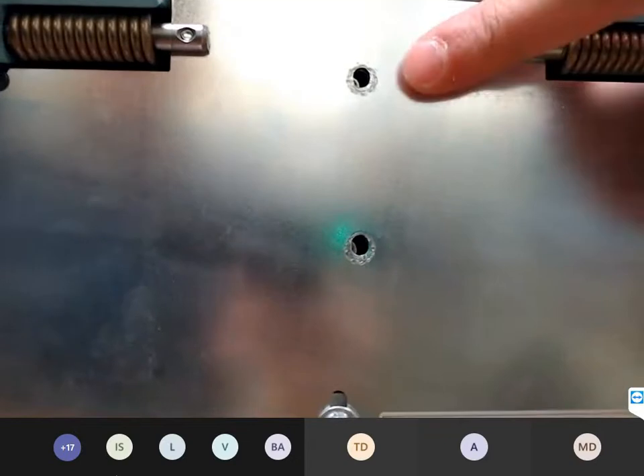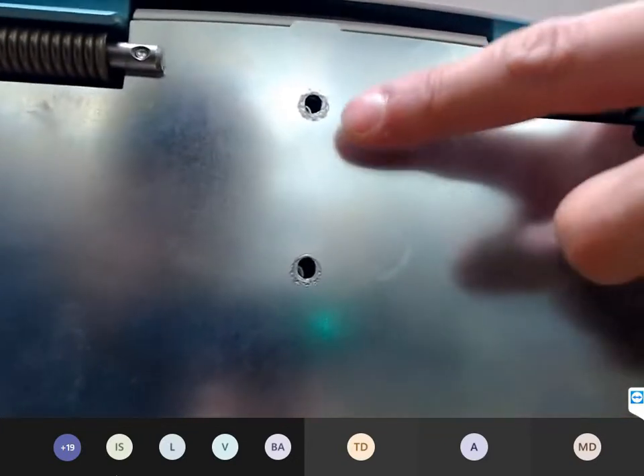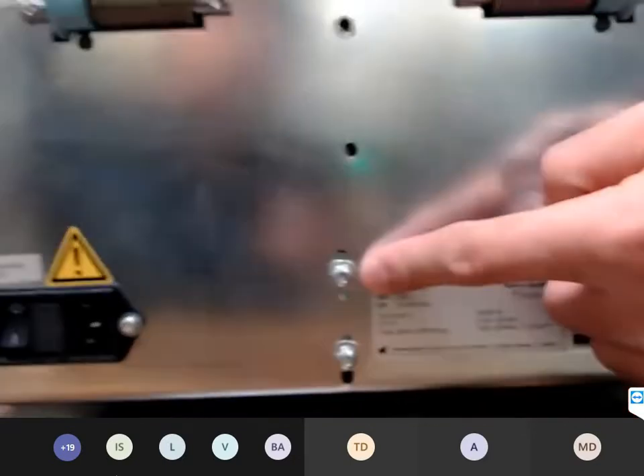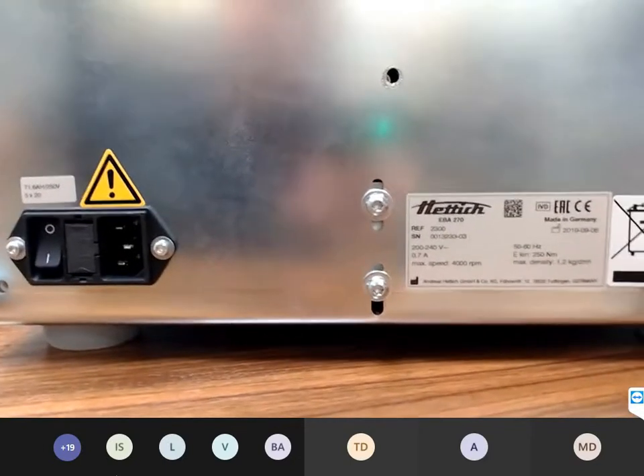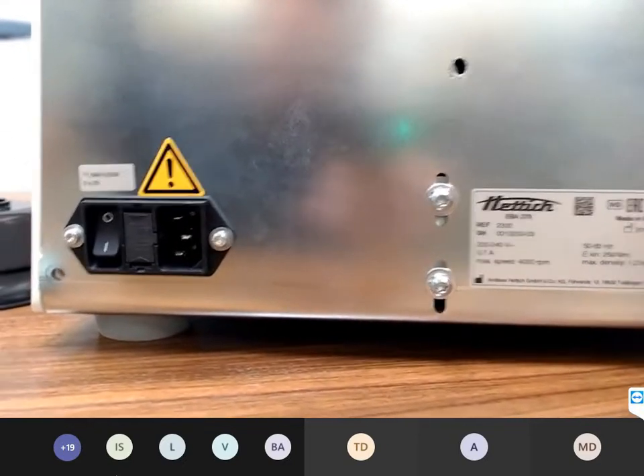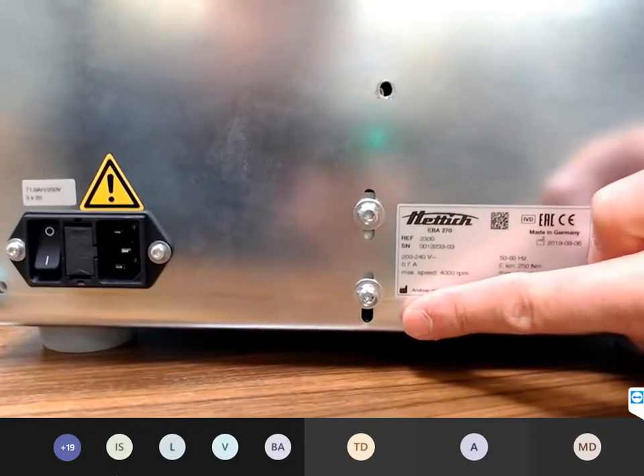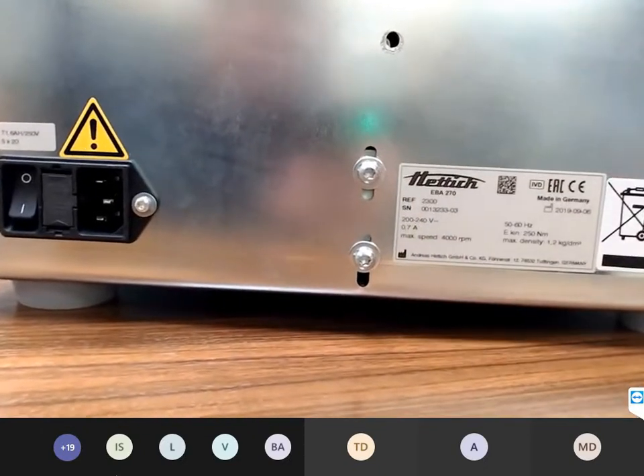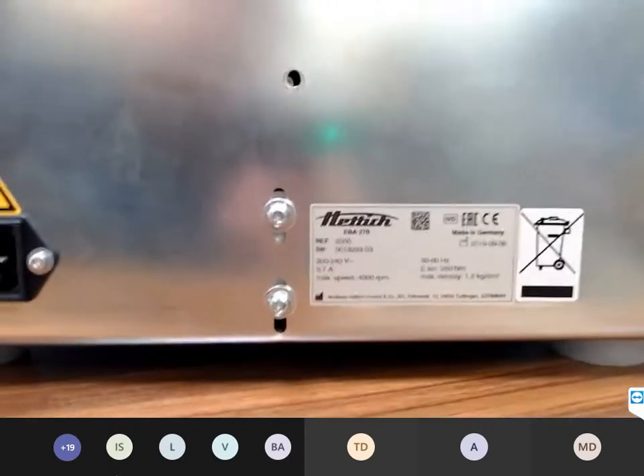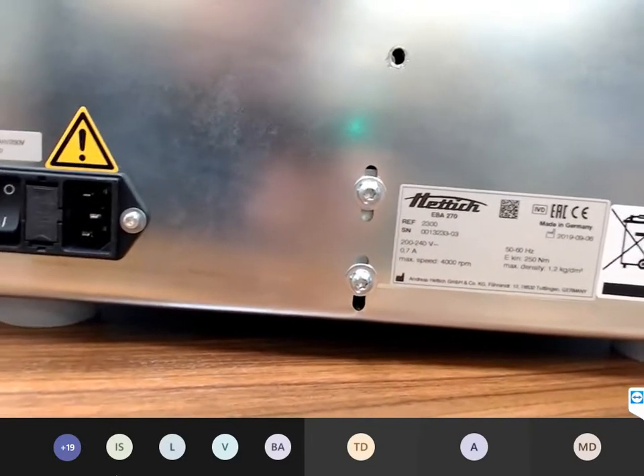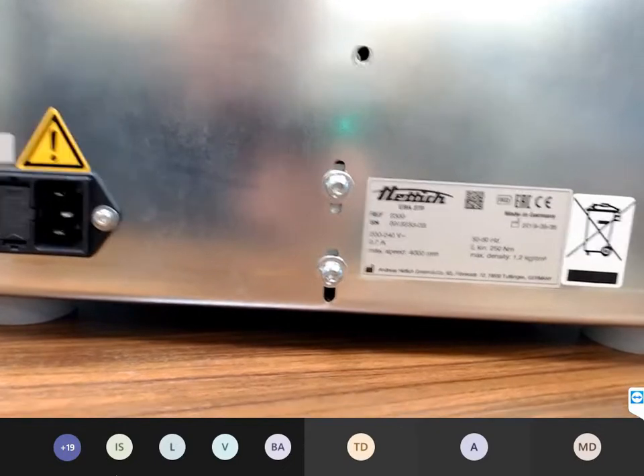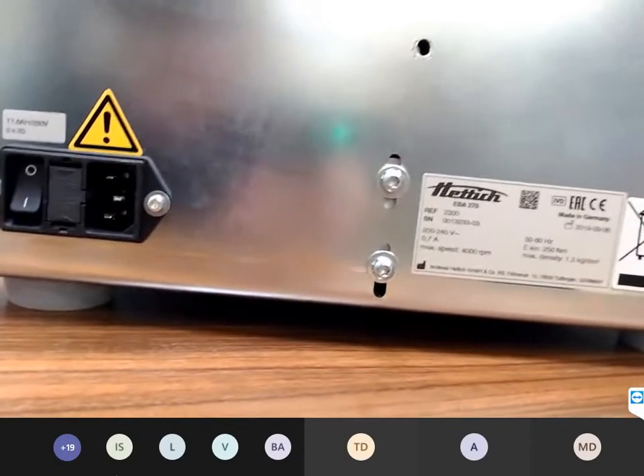On the back side, we have also unscrewed the two screws here. Very important, if you don't work with the imbalance sensor or you don't replace the imbalance sensor, please don't remove these two screws. You can see the holes here. This is for the setting adjustment of the micro switch for the imbalance detection. We have a mechanical imbalance detection via micro switch here.